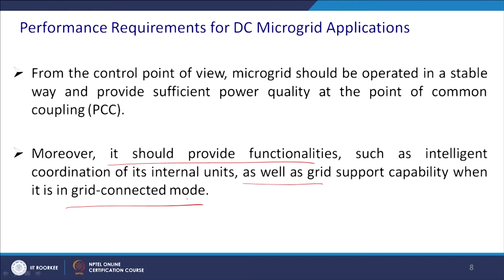Performance requirements for the DC microgrid application, from the control point of view, can be summarized as follows. Stability: the DC microgrid has to be stable, and for this reason we have stabilizing elements like ultracapacitors and batteries, and it has to be controlled properly by droop control or any other method. That means sufficient stability margin during normal and transient operating modes. When there is a load change, it should not throw the system into instability. Power quality: that issue comes into the picture at the point of common coupling, where the grid and the microgrid interact. There you should not inject harmonics. Also, a satisfactory voltage waveform in the common DC bus.